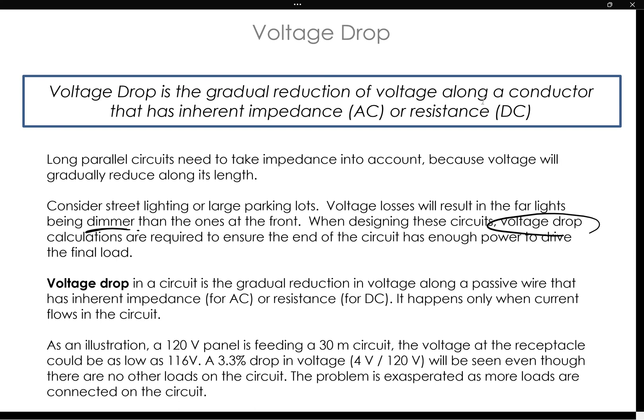The definition of voltage drop is the gradual reduction in voltage along a passive wire that has inherent impedance or resistance. It happens only when current is flowing in the circuit. As an illustration, 120 volts feeding a 30-meter circuit could have a voltage drop, making the voltage at the receptacle as low as 116 volts.